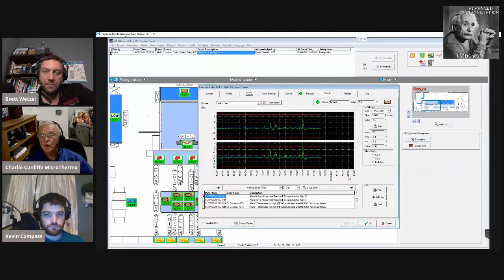That's how tight it is. So here's another cool thing you can do: trend graphs. Somebody's already set this up, so here's your control temperature and here's your circuit control temperature calls for it. You can build a total of 7 graphs within any of our nodes, and then you can save it in history. So if you've got a bad actor and you need to come back to the store in another week or another month, you don't have to recreate all these graphs again - it's saved in history, and you pull it up when you have to come back and troubleshoot. It's already there for you.